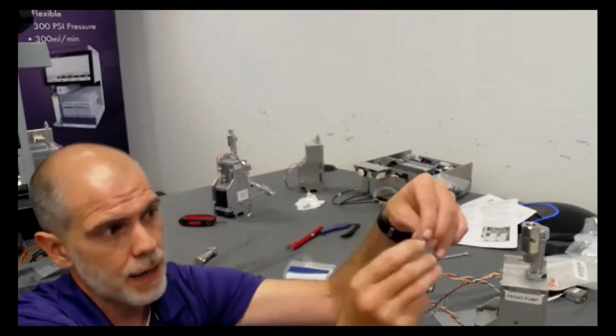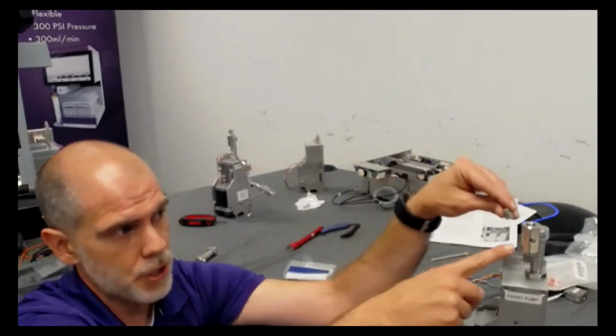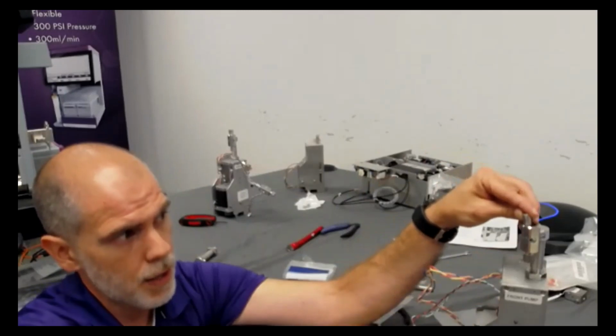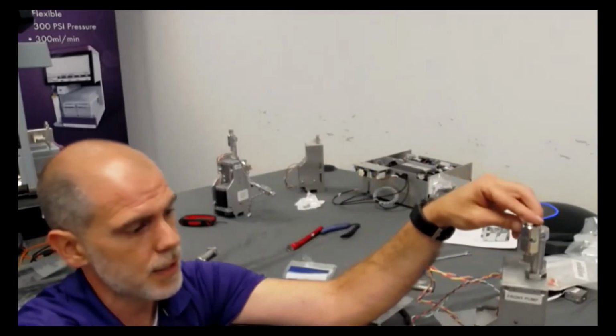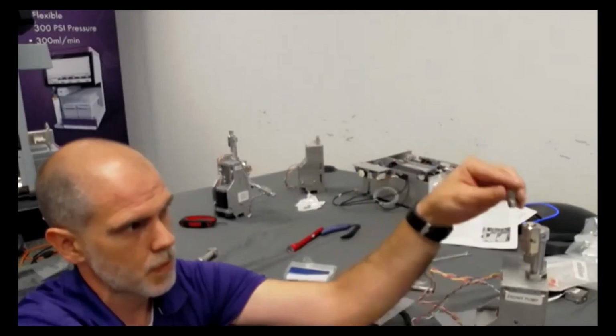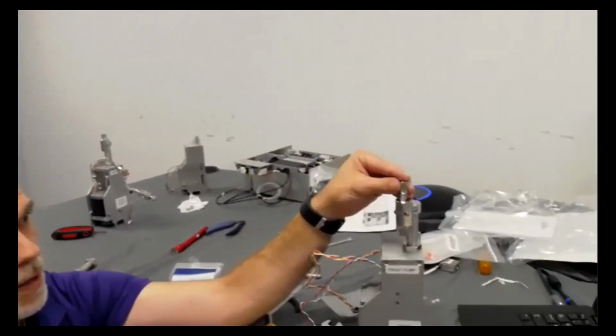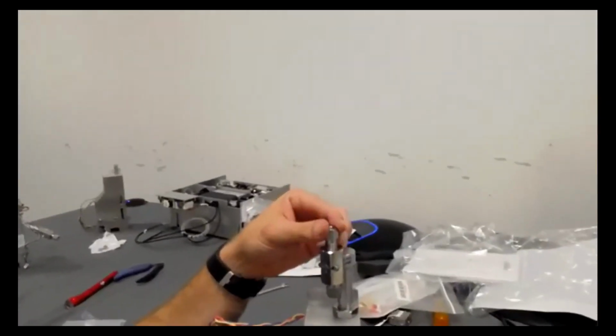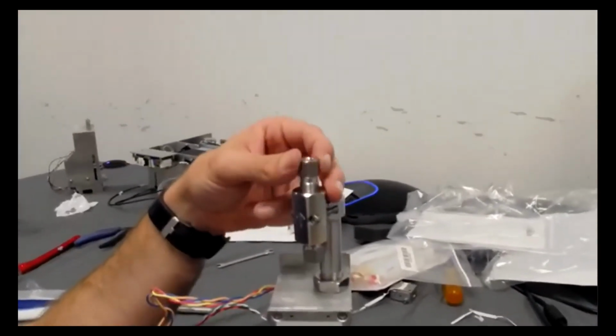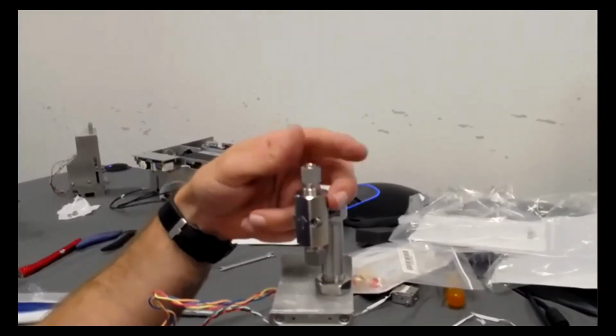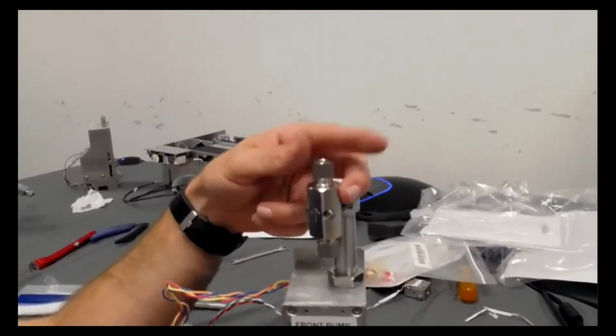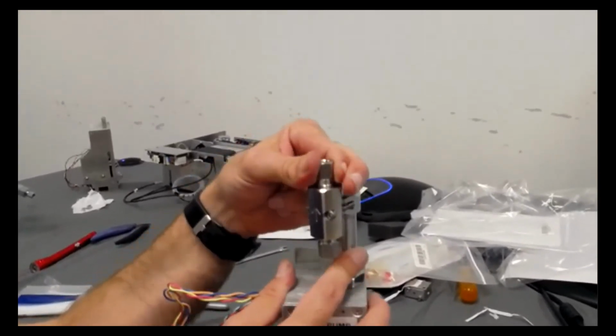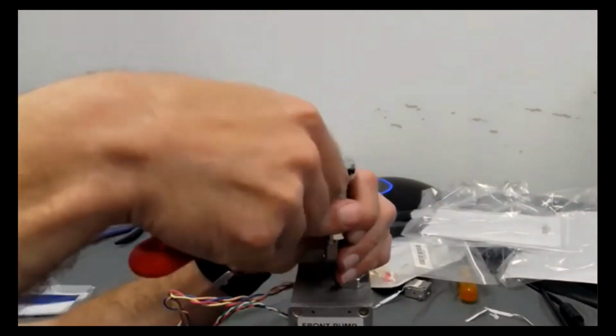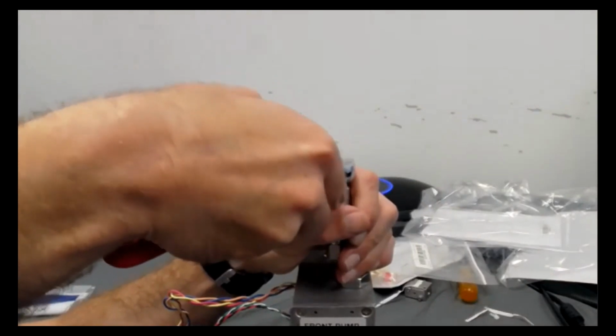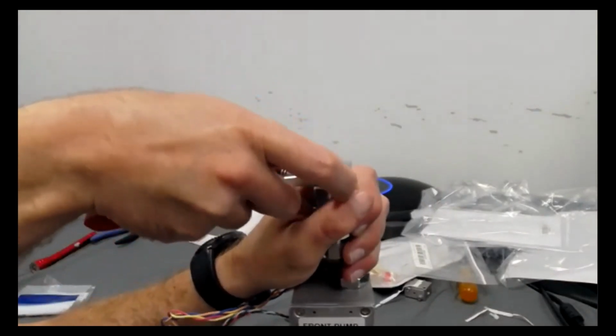When you go to put them back, make sure the arrow on the check valve cartridge is pointing the same way. So I'm going to slip that in there just now like this. And you can overtighten this as well. And if you overtighten this, you squash your check valve. That's bad. So okay, that's good and hand tight. So I'm going to finish it off. Just a slight tightening here. Boom, done.